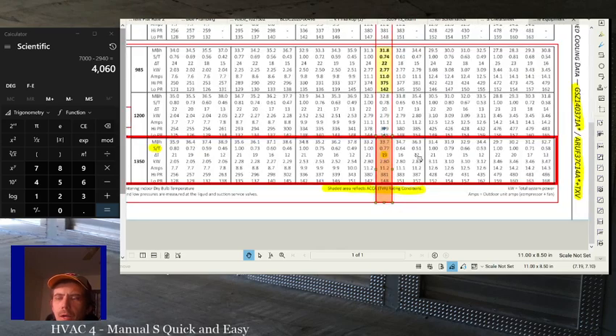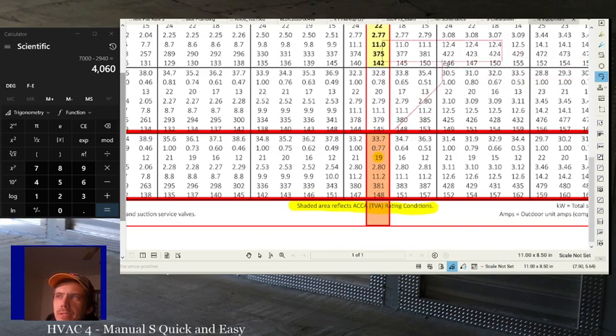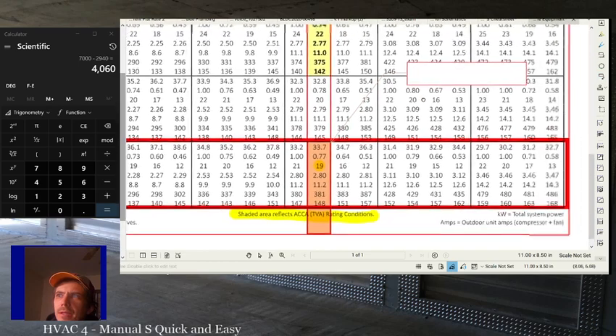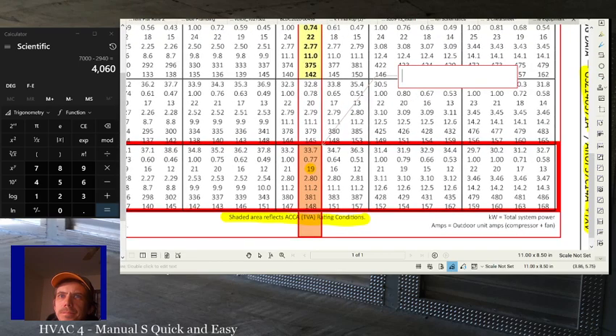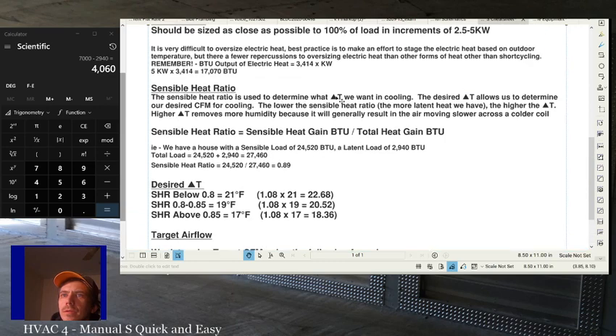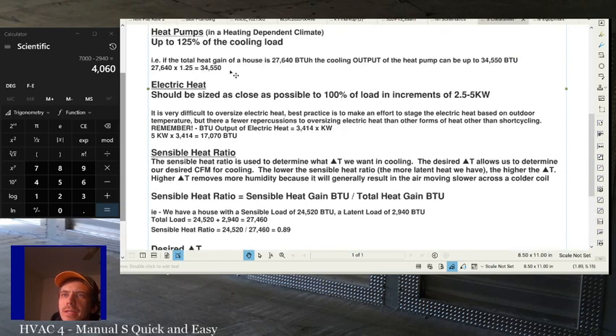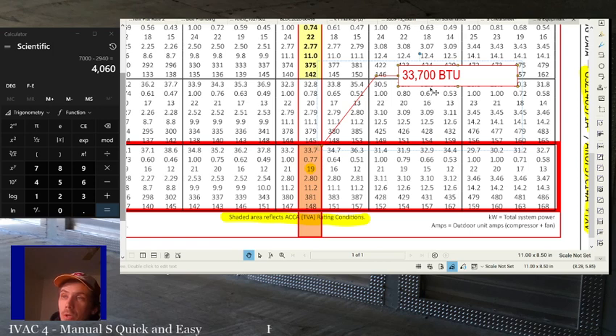All right, so that 33,700 BTUs, let's go ahead and put that down. So this equipment at our design conditions does 33,700 BTUs. So if we were picking a heat pump, that is less than the 34,550, so we would be okay. I used the same numbers for the example for the heat pump. So if we were picking a heat pump, this would actually be fine. We're pushing it, okay, but it would be fine. So we can go ahead and say, okay, yeah, it's 33,700 BTUs total.